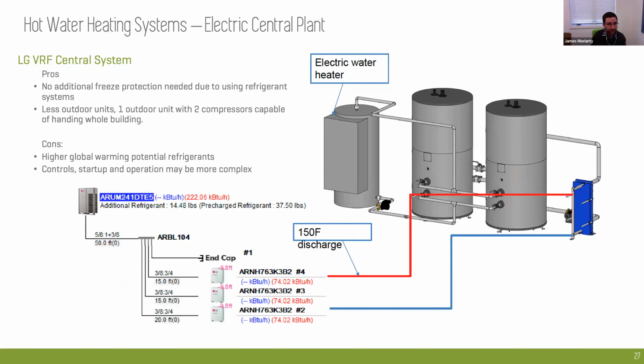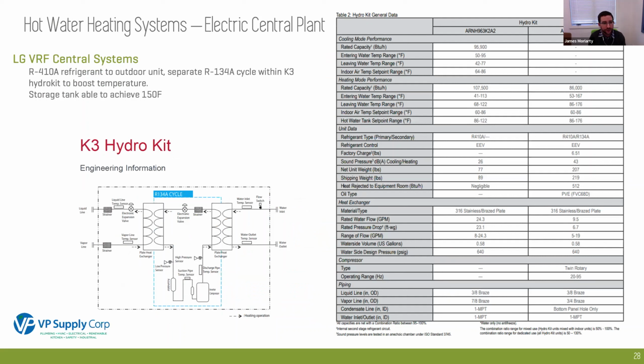So how does it work? You have the outdoor unit. It comes into these K3 hydro kits, and then it additionally boosts the temperature. The pros is you don't need to run hot water out of the building, and you have less outdoor units. The cons being you're now putting refrigerants back in. You have the higher global warming potential refrigerants, and then the controls and operations to keep in mind on those as well.